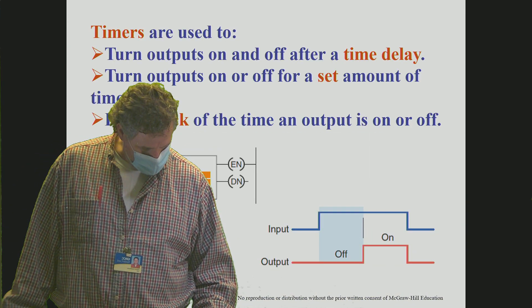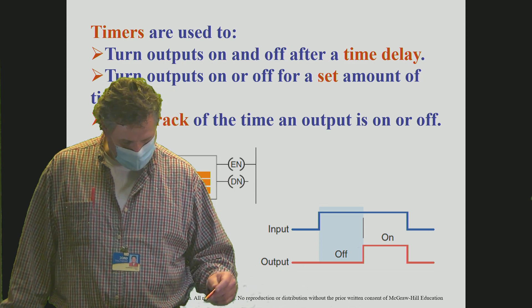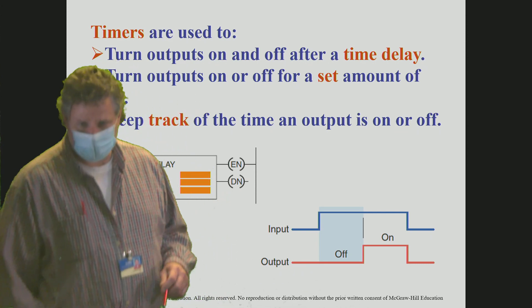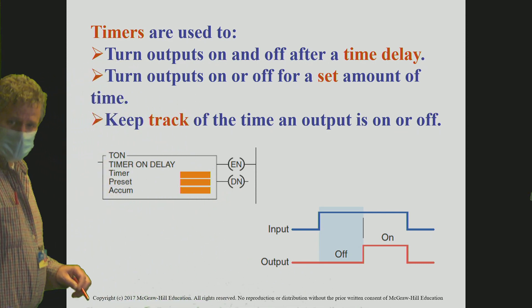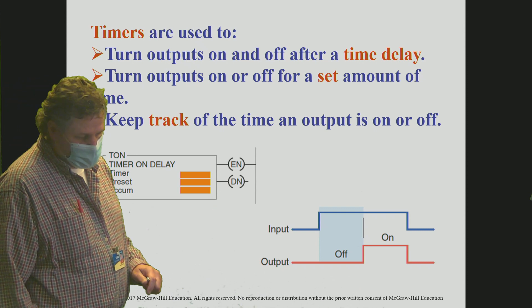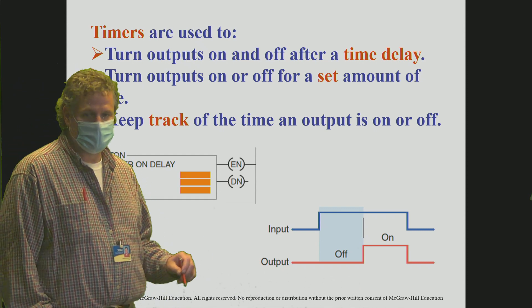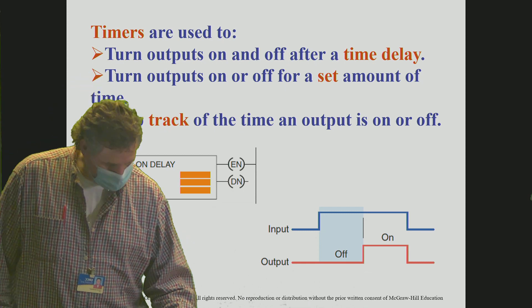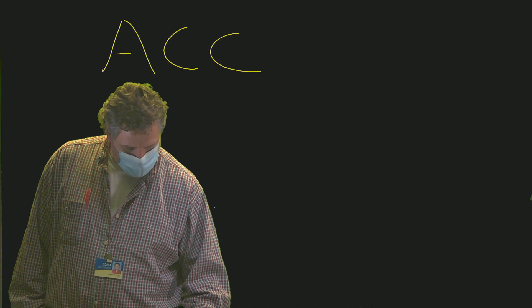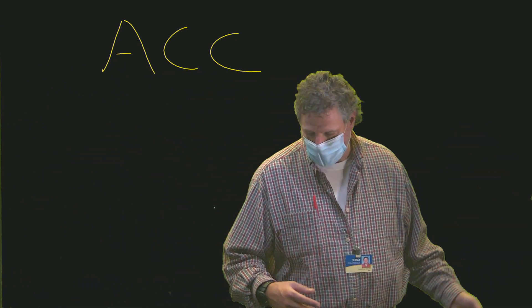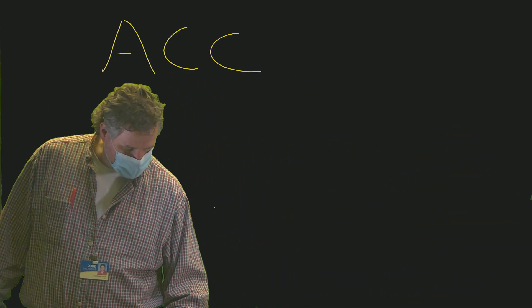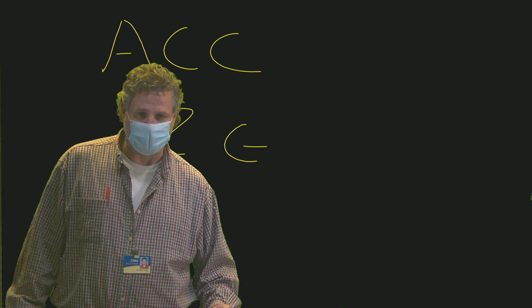Let's look at some of the details of how the timer works. Looking at the basic operations of the timer, keep in mind that the time-on-delay uses three pieces. The accumulated value is the value that is timing — it's a 32-bit word so it's a much larger value. We've got the preset, which is the point at which the output is going to turn on — that done bit will turn on.